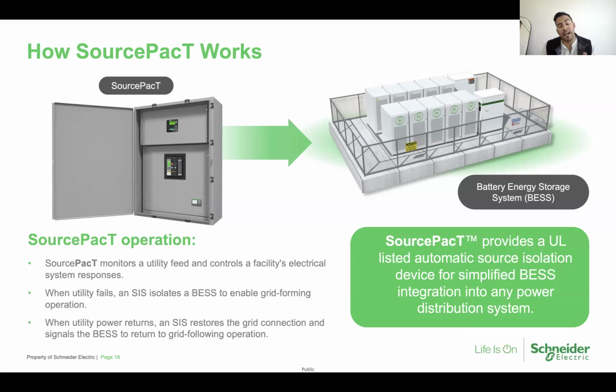So it safely isolates a portion of your facility so that microgrid systems can provide power to those essential loads, as Victor talked about in the National Electric Code. Of course, when we're isolated and the utility returns, that motorized breaker within SourcePacT remains open. So once we detect voltage and frequency are acceptable, there's a time delay setting in the controller that allows us to decide when we reconnect back to utility.